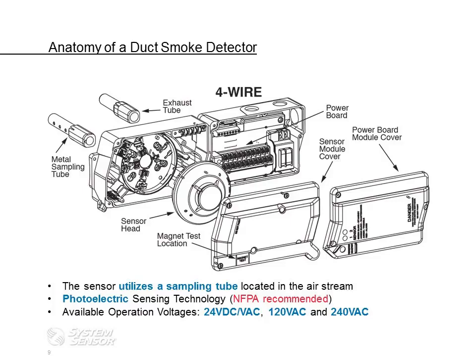The anatomy of a duct smoke detector: what you see here is basically a blown up diagram of all the parts and components of a duct smoke detector. The sensor utilizes a sampling tube that's located in the airstream. Then it has a smoke detector head, a photoelectric sensing technology head that's inside the housing. The available operating voltages are 24 volts DC and AC, 120 volts AC, and 240 volts AC is also available in a different version. We don't see very much 240 used domestically in the U.S., but there are some applications and some requirements internationally for 240 volts. That model is available if you do have that requirement.